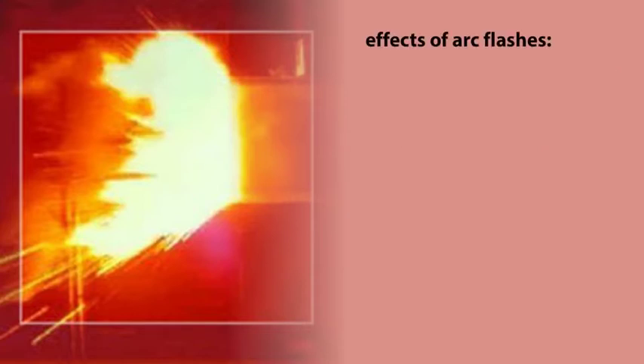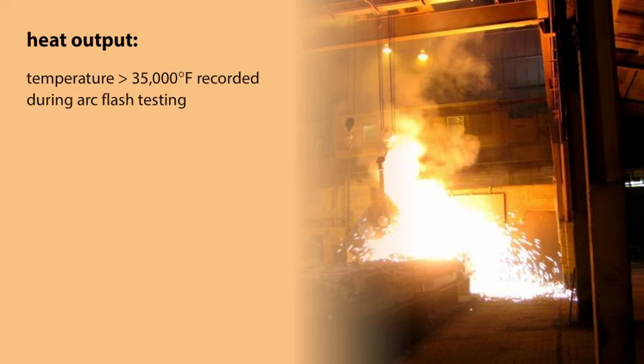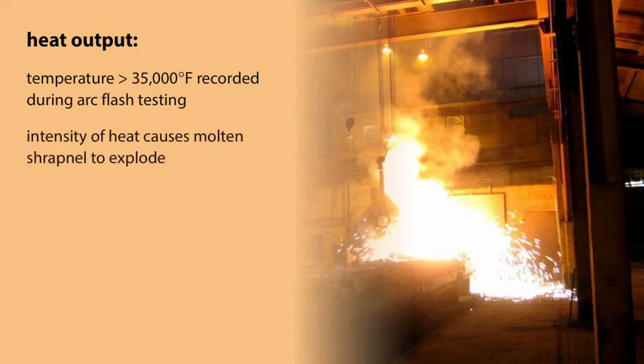The effects include heat output, thermal radiation, and pressure wave. First is heat output. Temperatures in excess of 35,000 degrees Fahrenheit—several times hotter than the Sun, which is 10,000 degrees Fahrenheit—have been recorded during arc flash testing. The intensity of the heat in the blast can melt metal, causing molten shrapnel to explode into the area surrounding the blast.